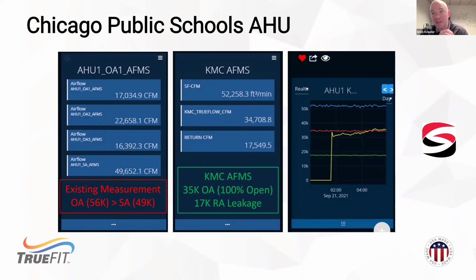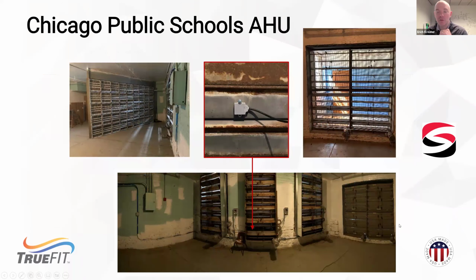The problem with that is, again, that did not account for any leakage that they're getting through the return dampers or the cracks in the doors or even the cracks in the damper louvers. If we go back to these pictures, we see quite a lot of light coming through those return dampers, and there's a couple bigger doors for access on either side that you'd see light come through as well.